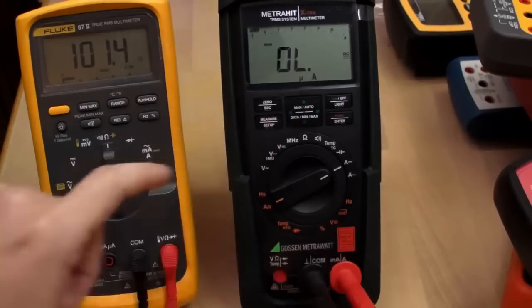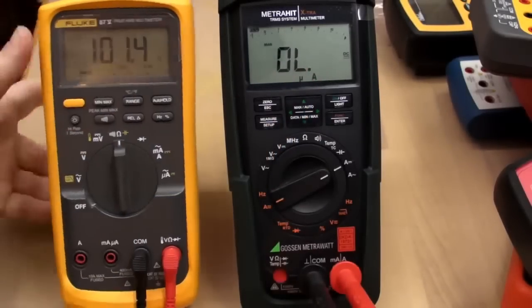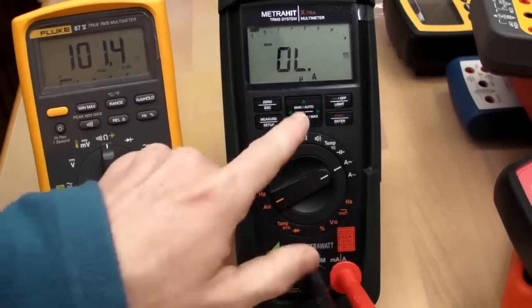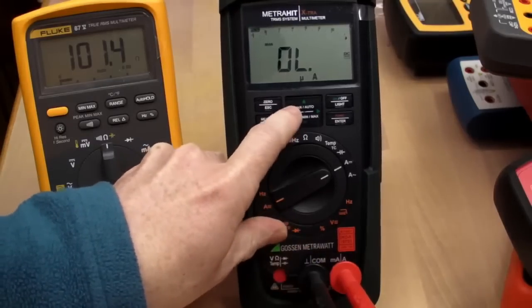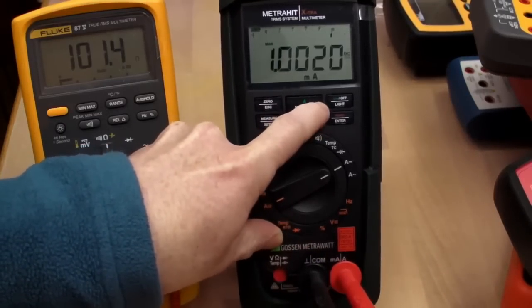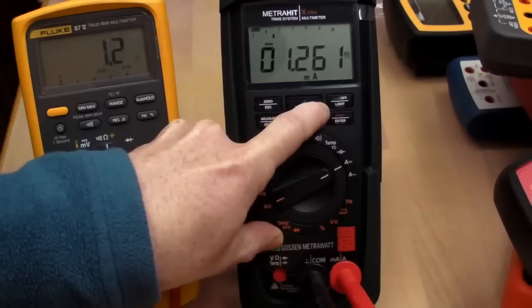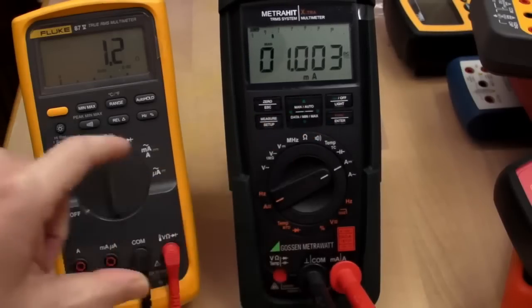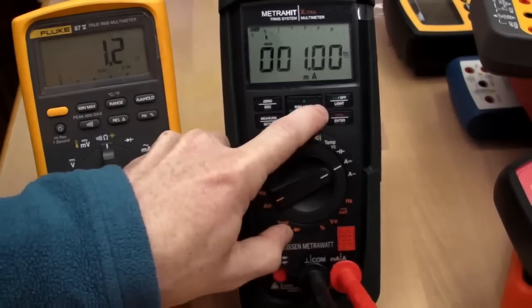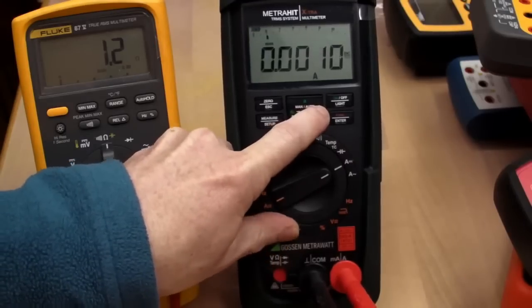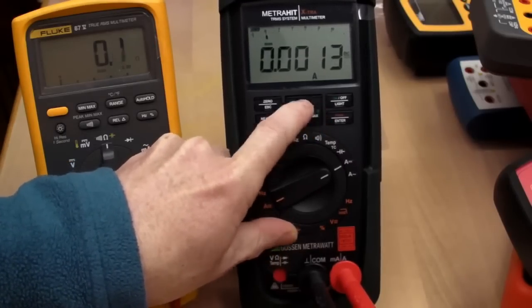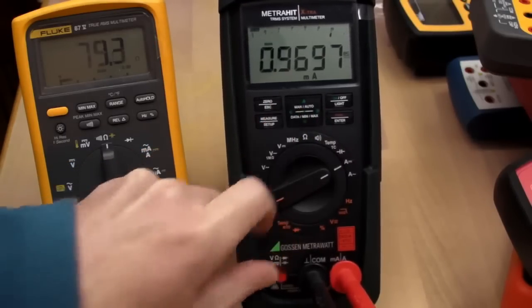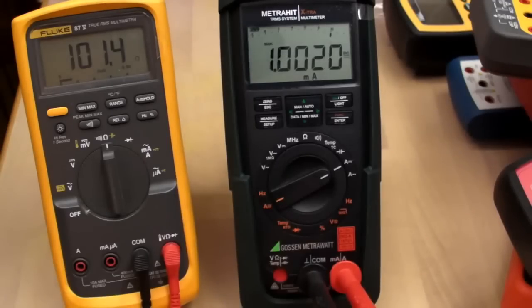I've got it set to microamps range, and we're measuring about 101 ohms, or 100 ohms basically. So that will be our reference value for the microamps range, and we'll see how the others compare. On the milliamp range, I've got basically 1 ohm, because I haven't zeroed out the test lead. So on the milliamps range, 1 ohm. On the microamps range, 100 ohms, and we won't worry about the amps range because all the meters are going to be very low on the amps range.